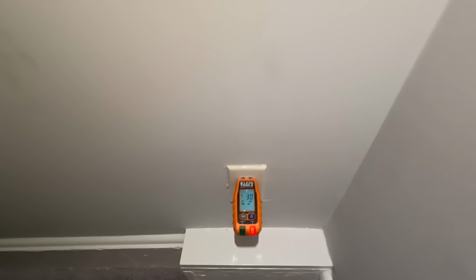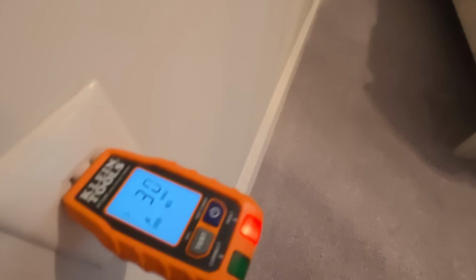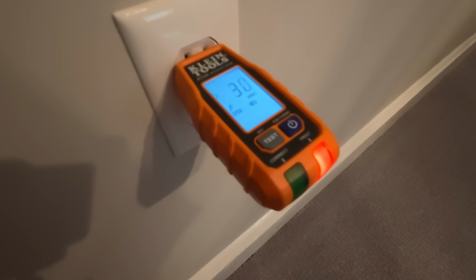Big fan. You'll see it says open neutral. So one of these receptacles in the room here has an open neutral that's not completing the circuit. All right, so it's safe to assume that this light on the ceiling is on the same circuit as these receptacles, but I don't know for sure. This one's also got an open neutral, so there's one down there and there's one right here.